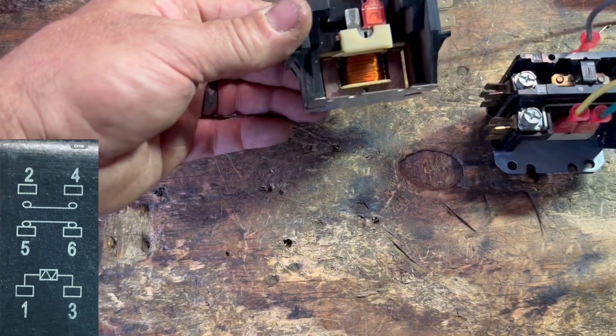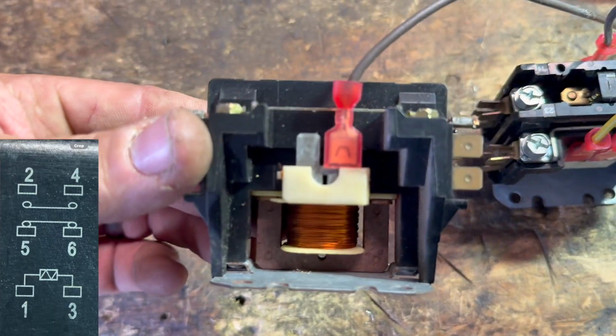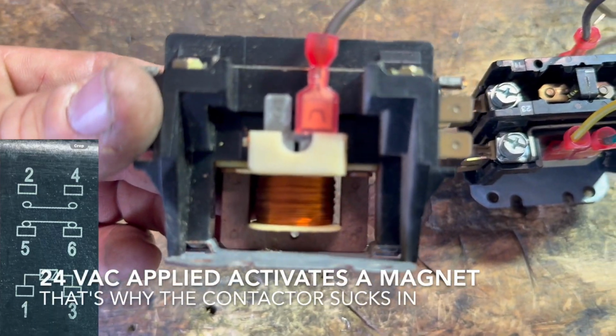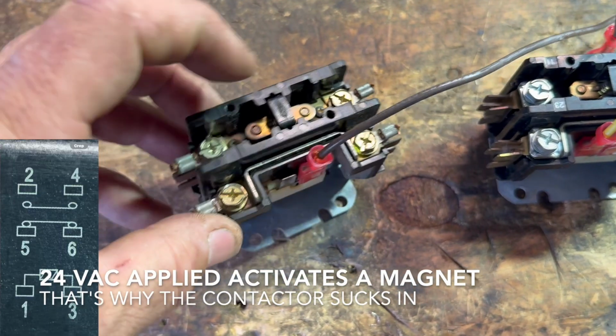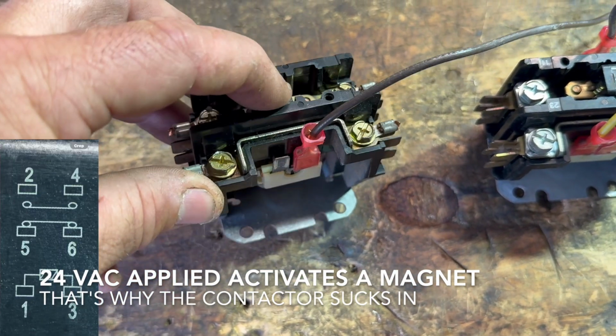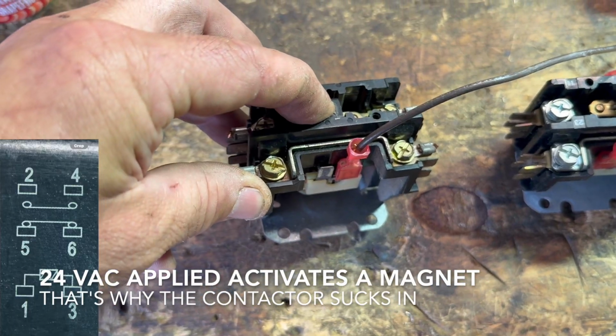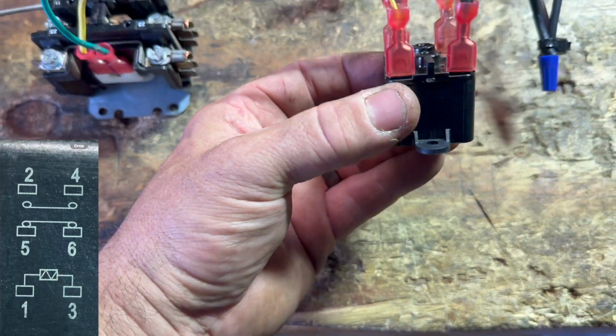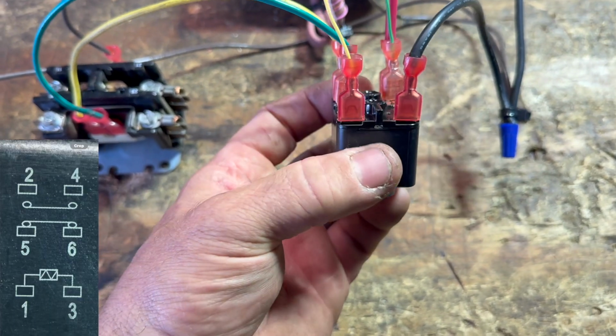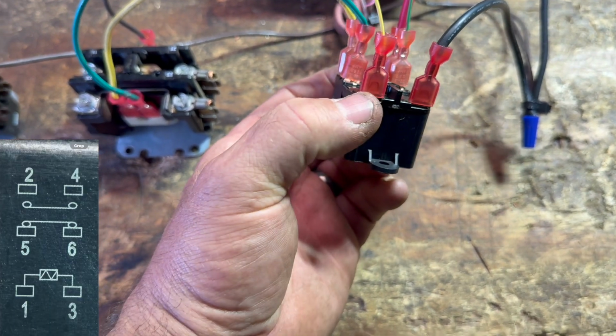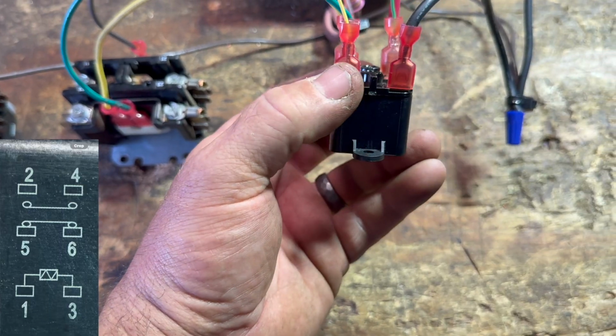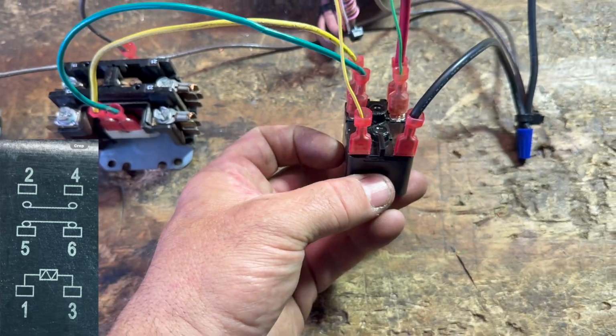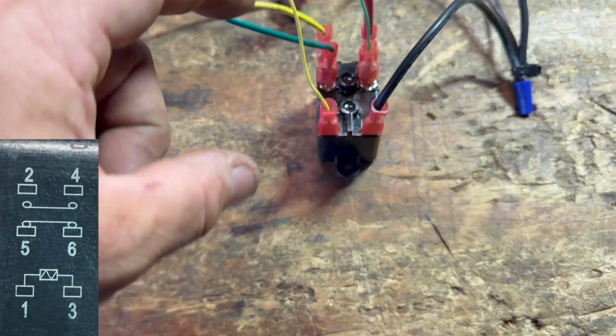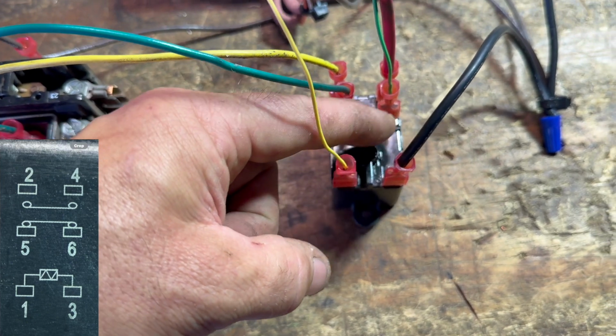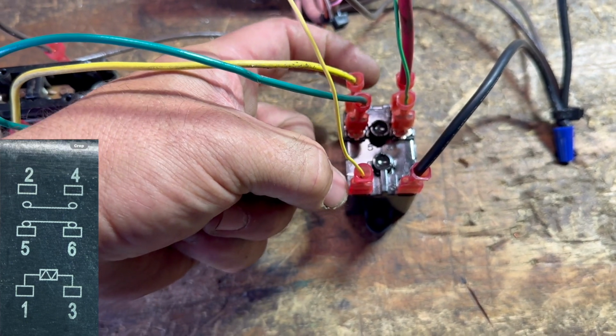And you can see here's one that's detached, but it's got a little coil down there. And so 24 volts makes it, when applied, close. And then when it's de-applied or unapplied, it opens. This actually has a small coil in it as well. So between 1 and 3 right here, these two end terminals, when 24 volts is applied, that coil will change the switch inside from connecting 5 and 6 to connecting 2 and 4.